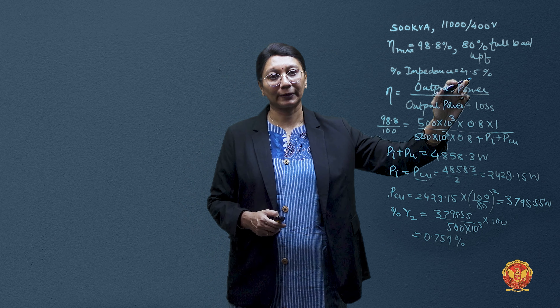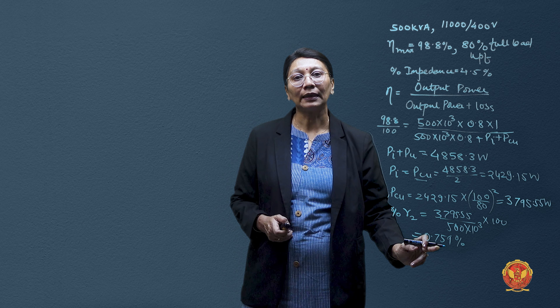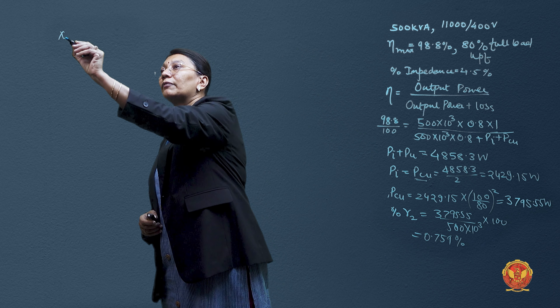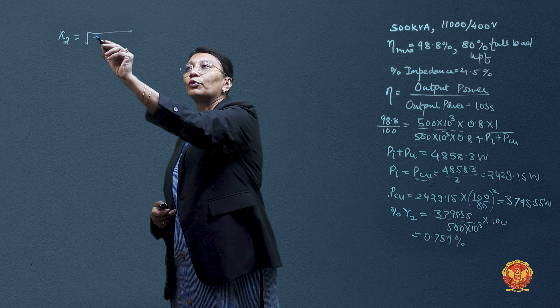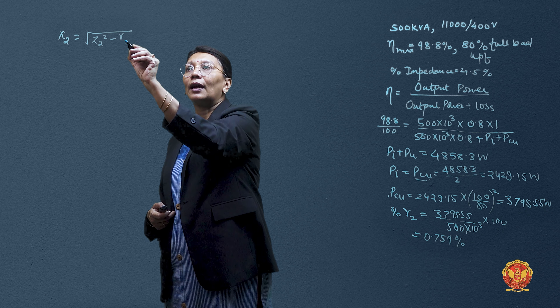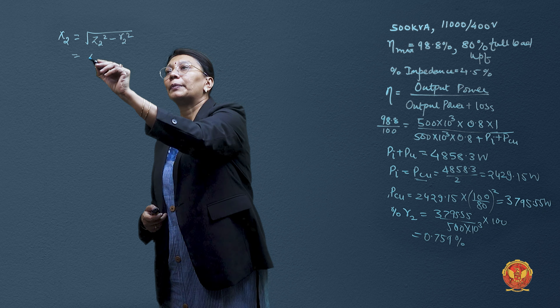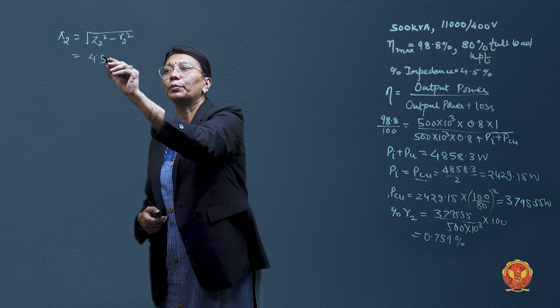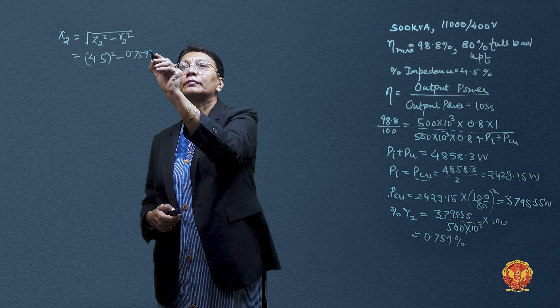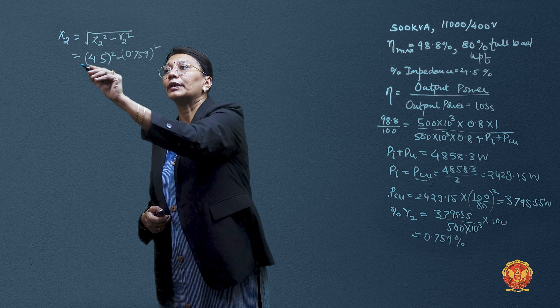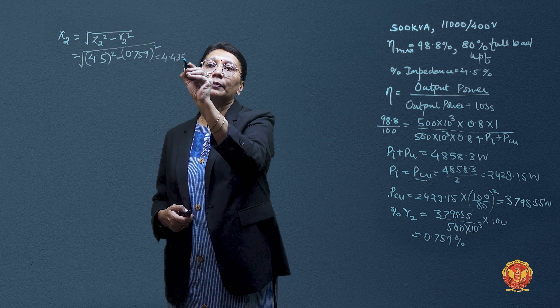With impedance Z = 4.5% and resistance R = 0.759%, we can find the percentage reactance using: X = √(Z² − R²) = √(4.5² − 0.759²). Taking the square root gives us a percentage reactance of 4.435%.